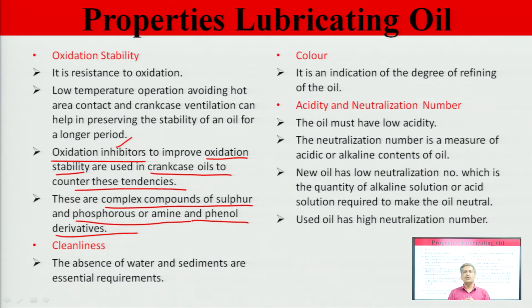Now, the last is acidity and neutralization number. What is acidity? The oil must have low acidity. The neutralization number is a measure of acidic or alkaline contents of oil. New oil has a low neutralization number, which is the quantity of alkaline solution or acid solution required to make the oil neutral. Used oil has a high neutralization number. So, the neutralization number should be low. As the neutralization number increases, that is why after a regular interval of time we always change the lubricating oil with a new one.